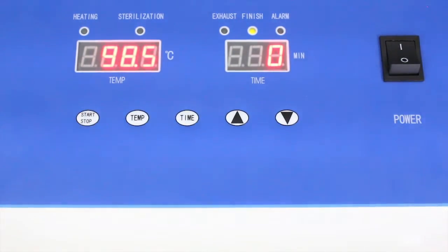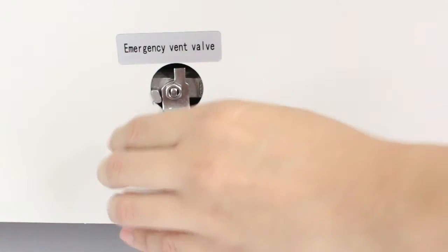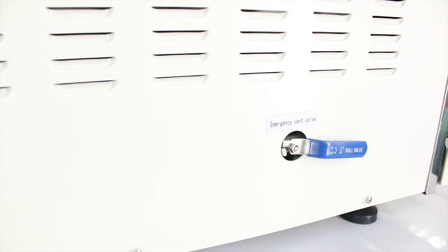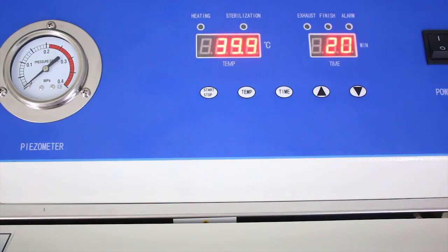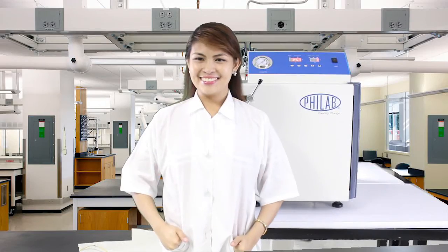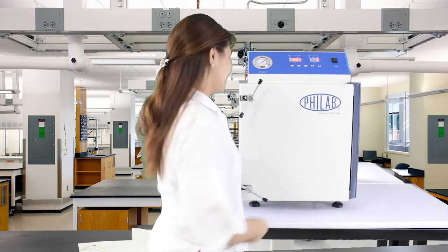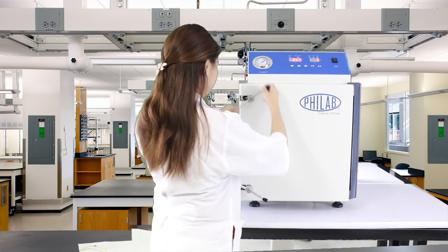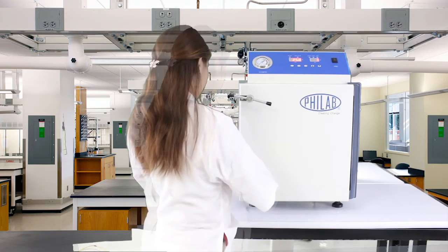Press stop. At this point, open the emergency vent valve found on the left side of the autoclave to release any remaining pressure. When the temperature has gone down to 40 degrees centigrade, you may safely open the chamber door. This ends the sterilization process.